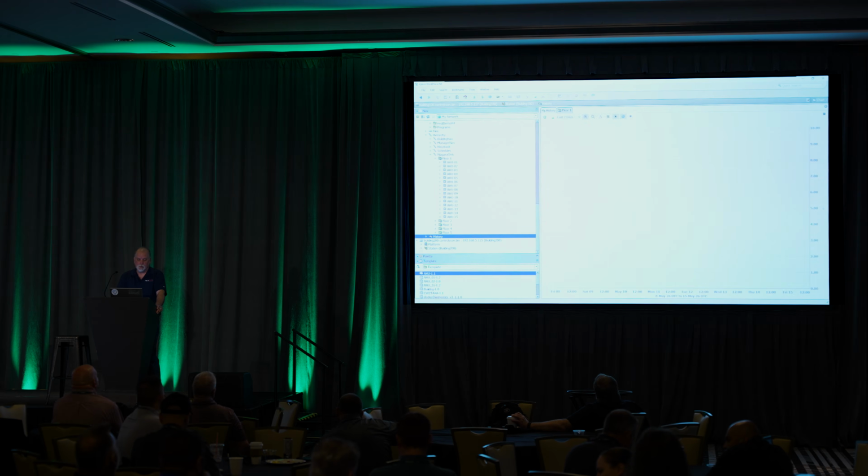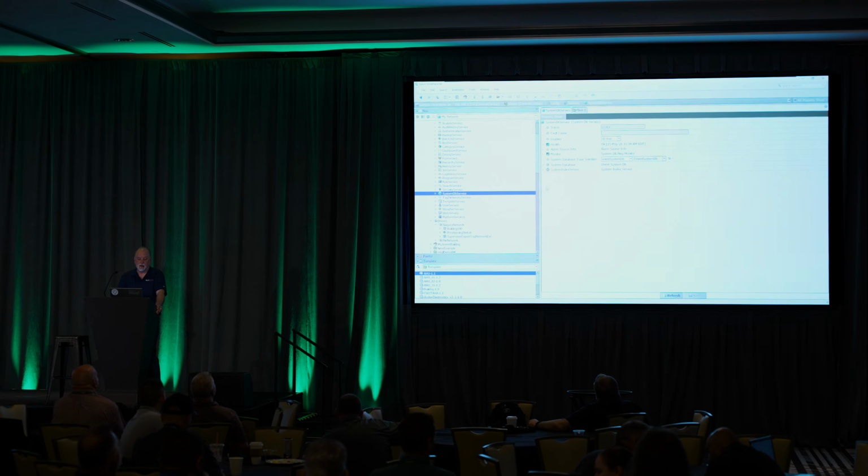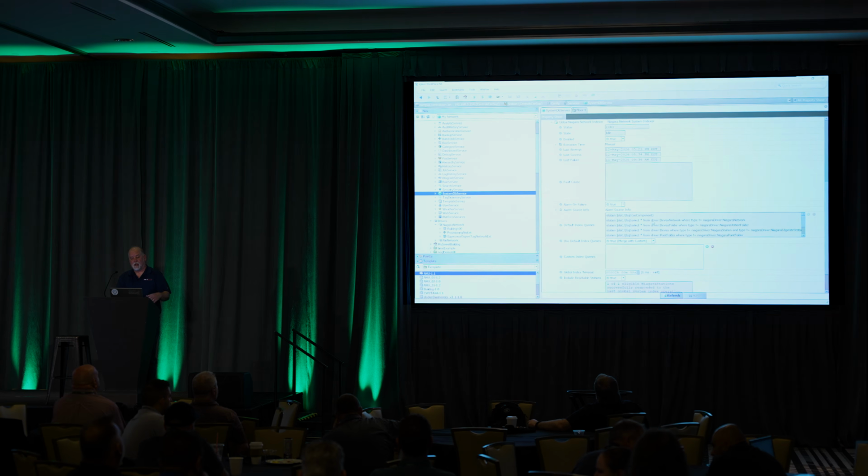Now, when we talk about system database, this is down in my JACE, and in the supervisor, we have something that's referred to as system database. And I'm not going to go into all the weeds here, but just understand that this system database is an Orient graph database, and we have these indexers that will run, depending on how you configure them, automatically or manually, and they go out and search those remote stations for things of interest, okay?